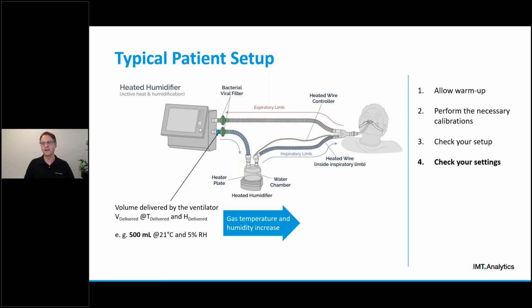Well, the temperature and the humidity of the gas are going to increase because we have a humidifier and a heated wire. What is the consequence of that? The volume is going to increase as well. So this means that in our example, the volume that actually reaches the patient is no longer the 500 ml delivered by the ventilator, but is now approximately 560 ml, because the gas temperature at the Y-piece is, let's say, in this case, typically 37 degrees Celsius and has a humidity of 100%.